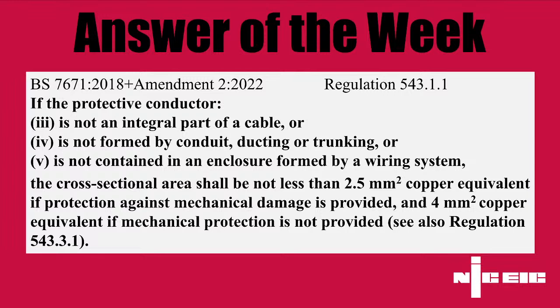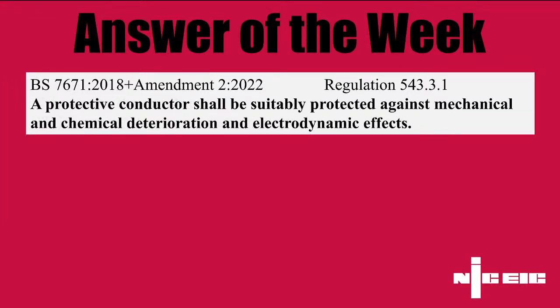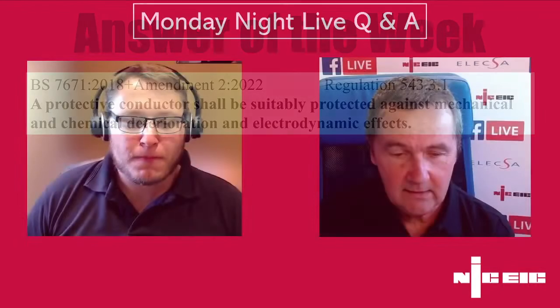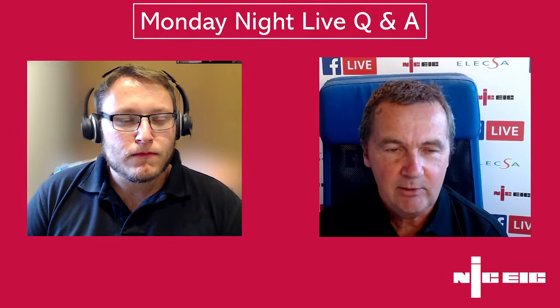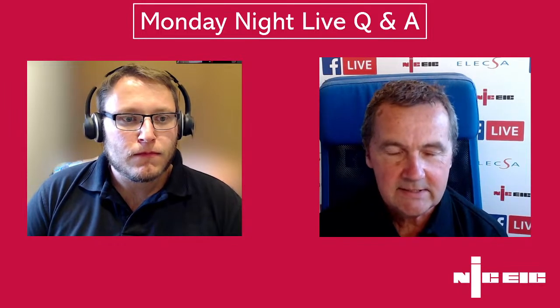While you're doing that, I'll also say that the last part of that reg talks about how we should also refer to 543.3.1, and that's a nice simple one, a short reg that says any protective conductor shall be suitably protected against mechanical and chemical deterioration and electrodynamic effects. So as you were saying, Craig, that's really the reason for that 4 mil, which might seem a little bit large for a CPC on a low current circuit, but a lot of it is due to the mechanical strength required, isn't it?